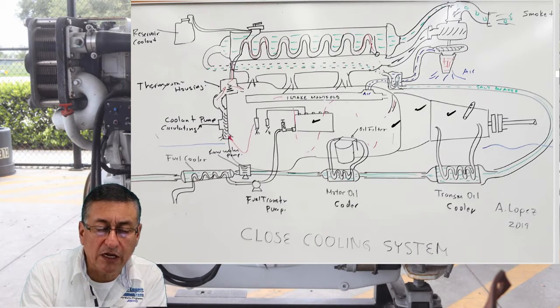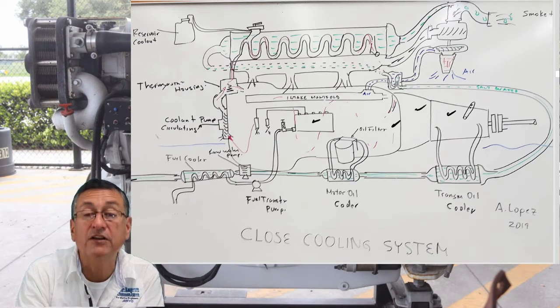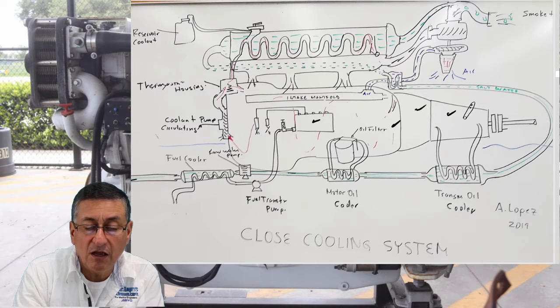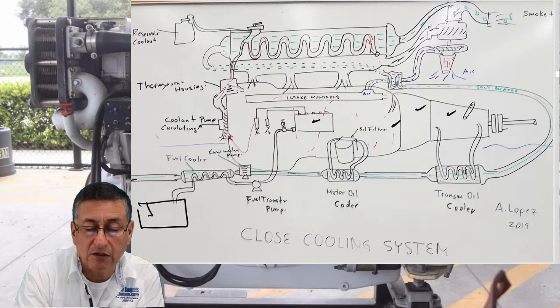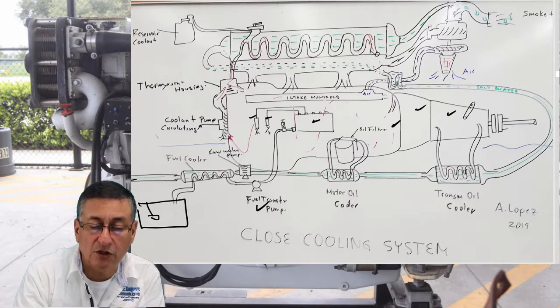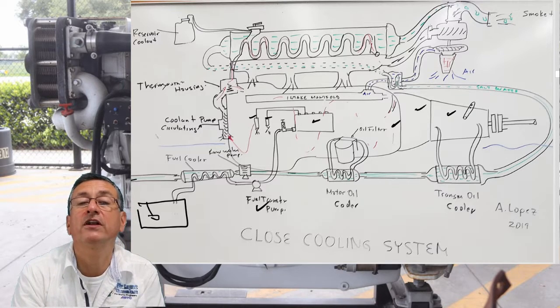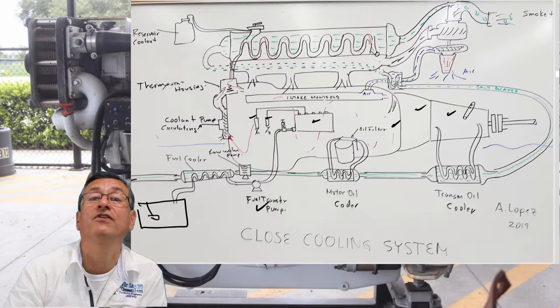This is the salt water coming from the sea-cock, entering here, and this is the first heat exchanger, the heat exchanger for fuel. That's the fuel coming from the fuel tank, located here. The fuel passes through the fuel transfer pump, enters the fuel injection pump, and enters the injectors. This first heat exchanger reduces the temperature of the fuel.